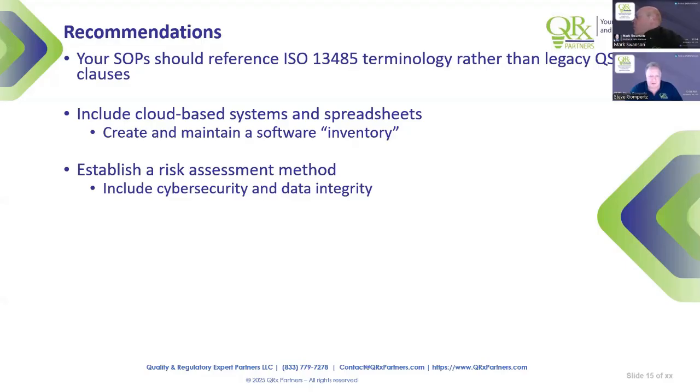But okay, you can't just say, yes, we're evaluating software for risk. How are you doing that? You do have to detail what our methodology for doing that is. And by the way, I mentioned some of the concepts of 14971, but they're not telling you to apply 14971. If you use FMEAs as a tool, they're not telling you you need to do an FMEA on all of your software, although they do mention that that's a possibility. If that's part of your strategy, that maybe for your higher risk tools you do perform an FMEA or something equivalent, you need to document what this methodology looks like, what our strategy looks like.